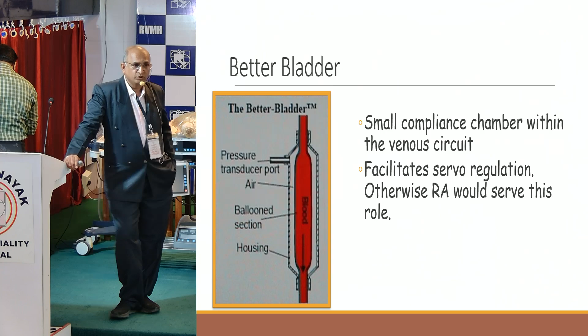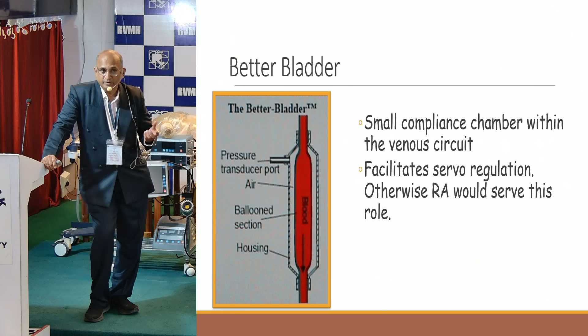Again, this is the venous bladder which we used to see when we used roller pumps. What is the role of the bladder? It is a collapsible bag. It acts like an RA outside. Whatever blood comes, comes first to the bladder and then goes on. When the bladder collapses, the machine senses it, as it is servo regulated, and the machine speed decreases or it stops. So you don't get too much suction effect in the RA and the endothelium of the vessel does not get damaged. It is the servo-regulated bladder which used to control it.